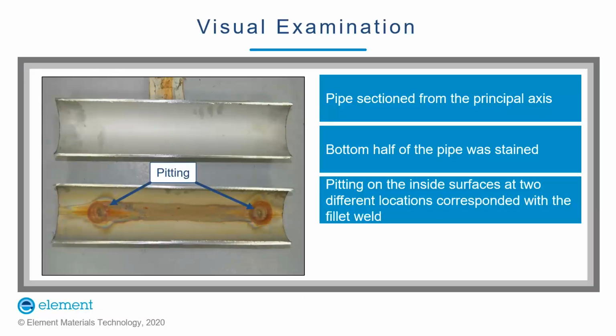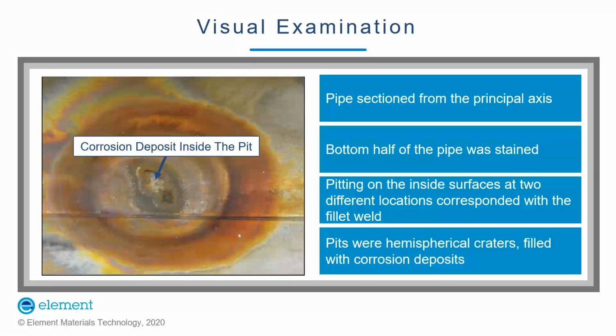Pits due to corrosion were observed on the inside surface at 2 different locations that corresponded to the areas where the pipe was fillet welded with the plate from the outside surface. As shown, the pits were hemispherical craters. The pits were found to be filled with corrosion product. Ring-shaped rust stains were observed around the pits, with deposits of reddish-brown corrosion product also observed. Similar types of pitting and corrosion deposits have been reported by different researchers in various stainless steel piping systems when the water in the pipe remained stagnant over a period of time.